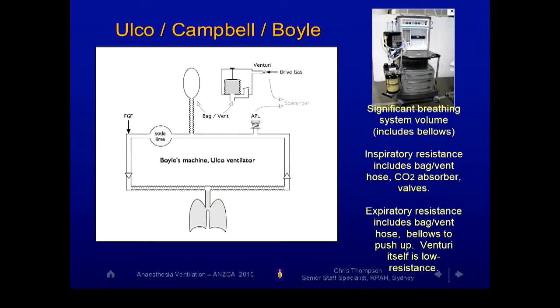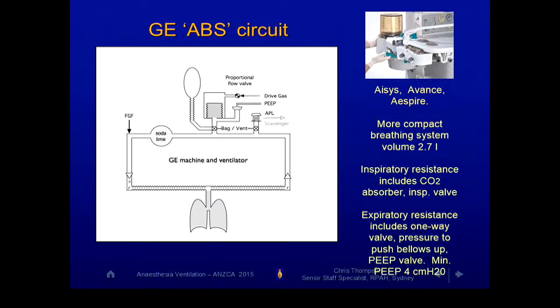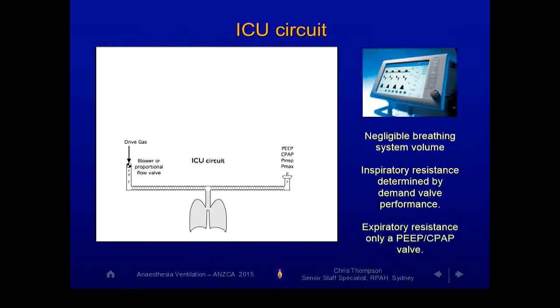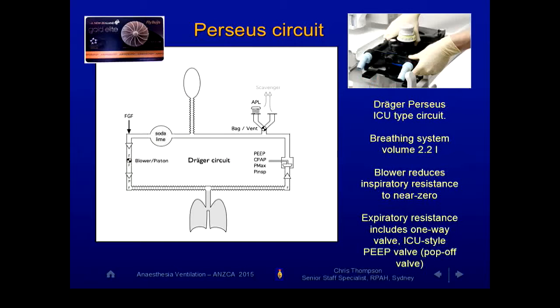So this is the machine that you're familiar with. It's still got the little patient circuit, goes round and round at the back. There's a big bottle of soda lime in the way. To breathe in, you've got to breathe through the soda lime. You've got to get it through a bag and extra tubing. So there's a bit more resistance. And when you breathe out, you can't breathe out once the bag is full until you crack the APL valve. And if anyone there thinks they're doing a favour to a patient by putting an APL valve on 5, they're not. It makes it harder. And then a GE circuit or any modern type bag and bottle ventilator is really just a rearrangement of the deck chairs of the old style machine. But what Dräger have done is, I just remind you of the ICU circuit, they've left the ICU circuit where it was. So that little bit on the left that says blower piston, this one has a blower, is the delivery of gas device.